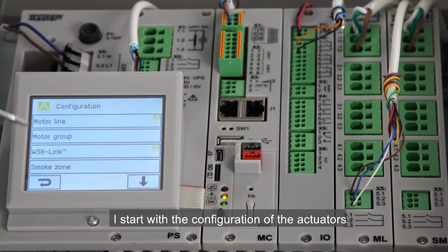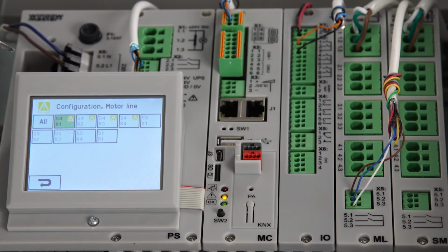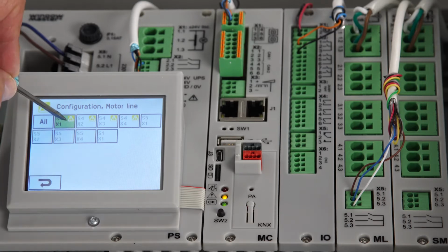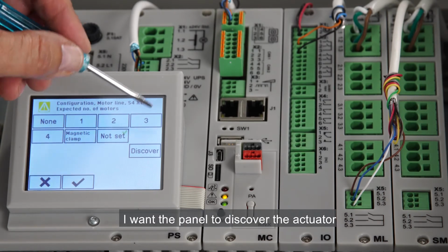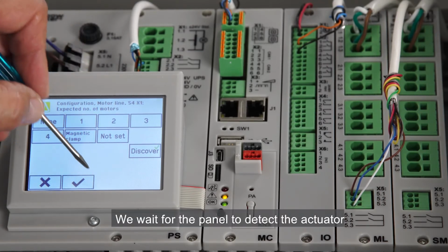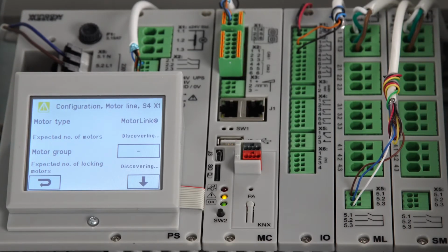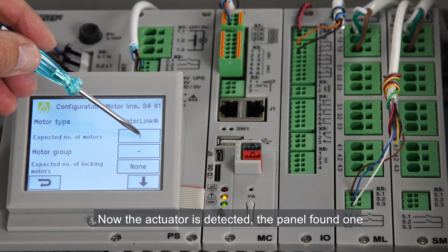I start with the configuration of the actuators. I press the motor line button. I have 2 motor lines connected. The first one that runs in motor link mode is connected at S4X1. Expected number of motors. I want the panel to discover the actuator, so I select Discover. We wait for the panel to detect the actuator. Now the actuator is detected, the panel found one.